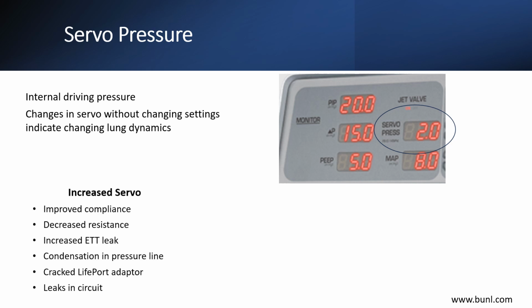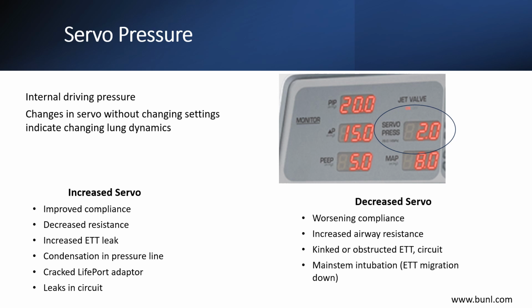Trending the servo measurement when no adjustments have been made to the settings can indicate changes in lung compliance and resistance. The jet ventilator will alarm high or low when there is a change of more than 20% above or below the baseline servo. An increase in servo pressures indicates that more flow is required to fill a space at the same peak inspiratory pressure. So, this means that for a given pressure, more volume is being delivered.